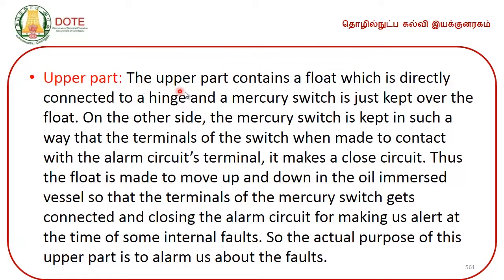Upper part. The upper part contains a float which is directly connected to a hinge, and a mercury switch is just kept over the float. On the other side, the mercury switch is kept in such a way that the terminals of the switch, when made to contact with the alarm circuit's terminal, make a closed circuit. Thus, the float is made to move up and down in the oil immersed vessel, so that the terminals of the mercury switch get connected, closing the alarm circuit for making us alert at the time of some internal faults. So, the actual purpose of this upper part is to alarm us about the faults.